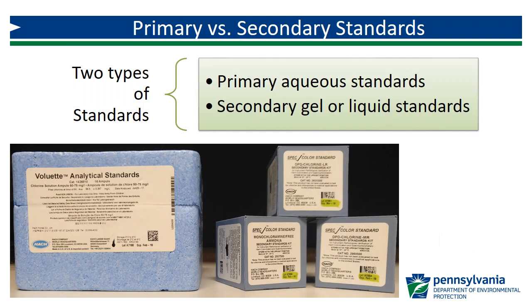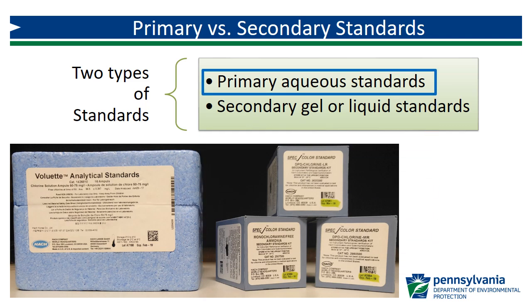There are actually two types of check standards discussed in Method 334.0: primary aqueous standards and secondary gel or liquid standards. Each standard has a defined role and specific requirements outlined in the method. In this video, we will focus on primary standards. Secondary standards will be covered in a later video.